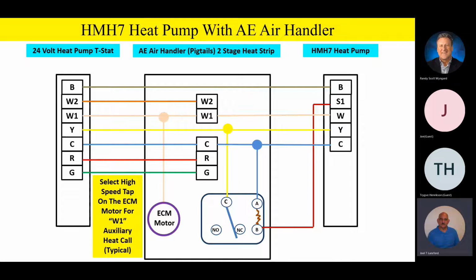Now, the contractor, if he did some airflow measurements and needed to adjust that, is perfectly capable of doing that. But I'm just mentioning this is typically how it's hooked up, where you have a defrost call W, or a W1 input from the thermostat. We're going to energize that ECM motor on high speed.